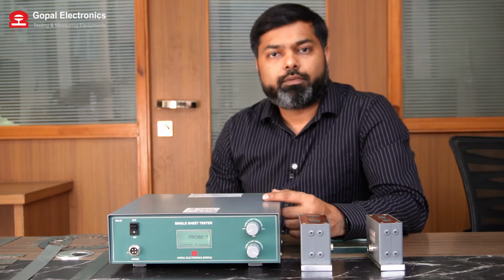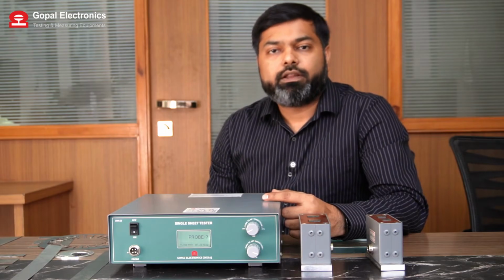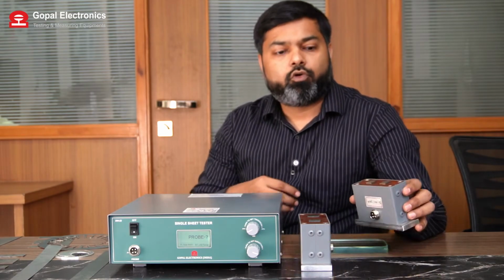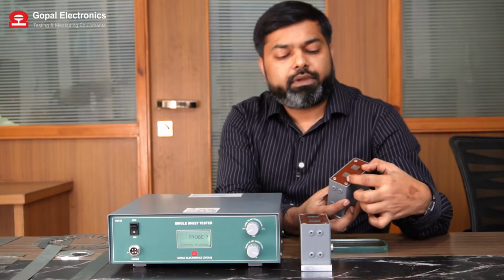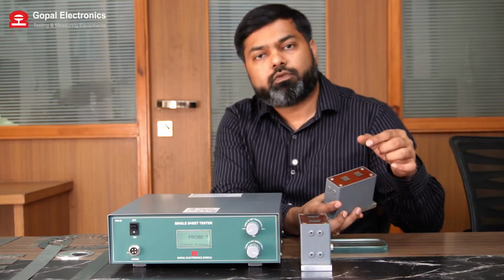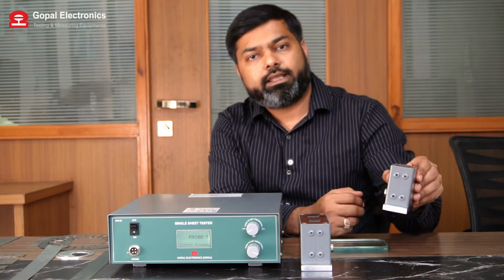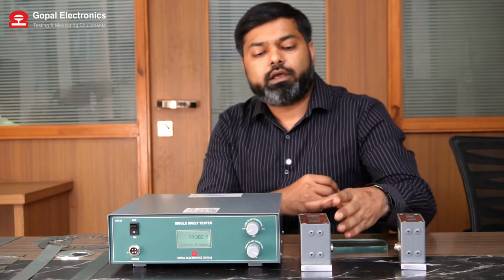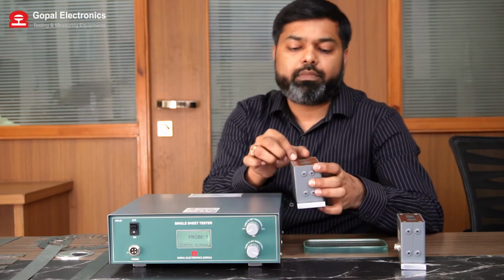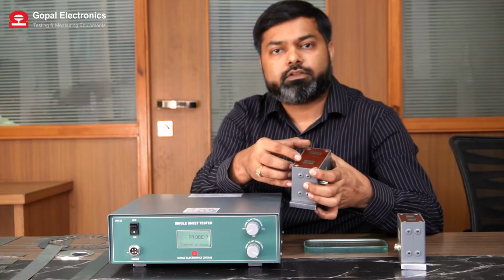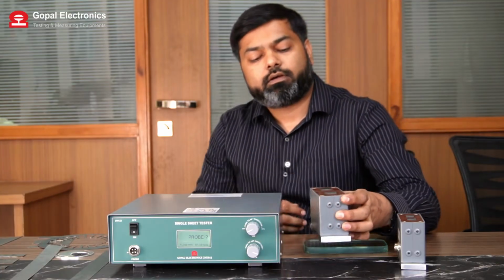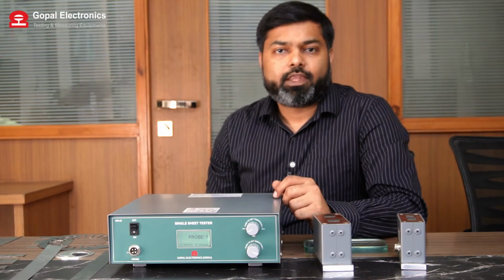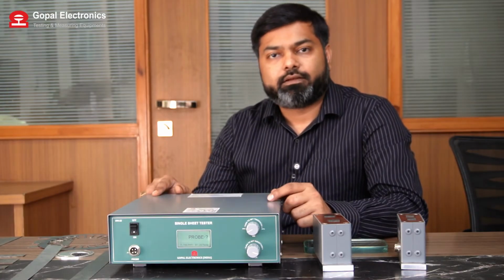Two types of probe option we have provided for different kinds of samples. Small probe core area is 40 mm by 14 mm, so this is suitable for motor stamping and EI lamination. Bigger probe core area is 20 mm by 60 mm, so this probe is suitable for transformer lamination. Now let me show you the testing method.